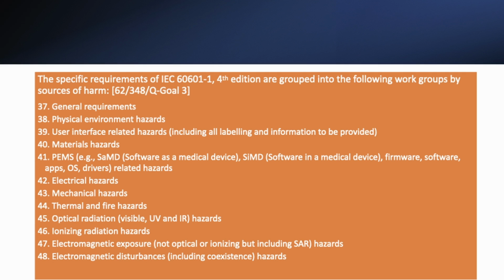The layout is here on the screen: general requirements, physical environmental hazards, including areas outside the professional medical facility, things like home and EMS, and user interface related hazards, the usability and the alarm systems. Material hazards: there are a lot of new novel materials used today in medical devices, plastics and other materials. Programmable electrical medical systems, meaning software in a medical device, firmware, software applications, operating systems, drivers. Also, the traditional starting point and home of IEC 60601, the electrical hazards, will still be a major factor in considering updates to the standard, looking at new ways to power and provide energy sources in medical electrical equipment.